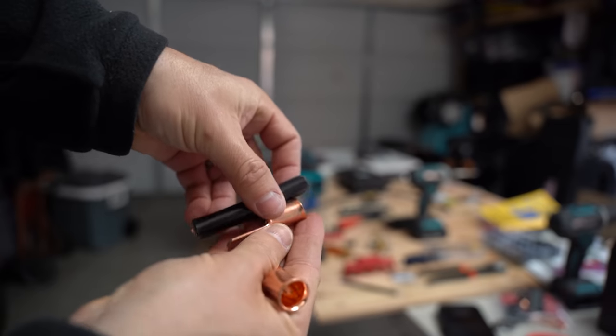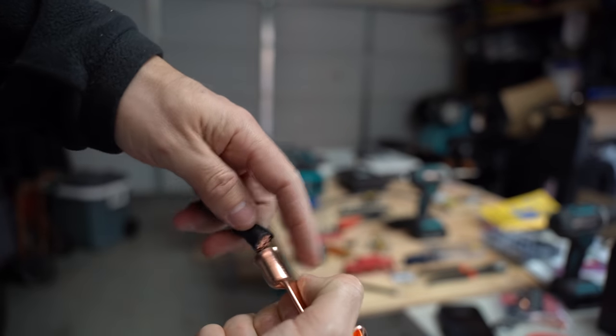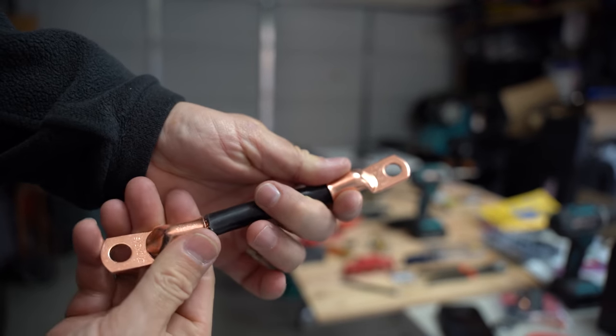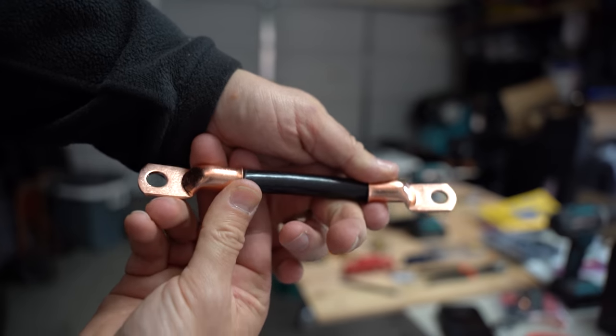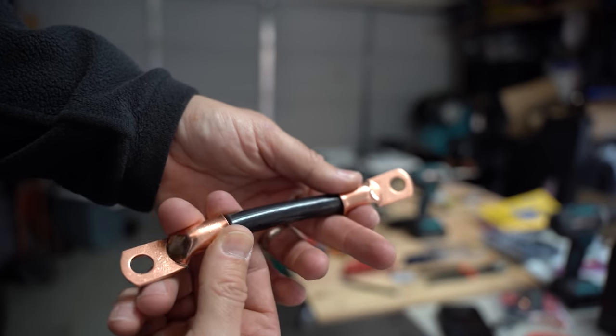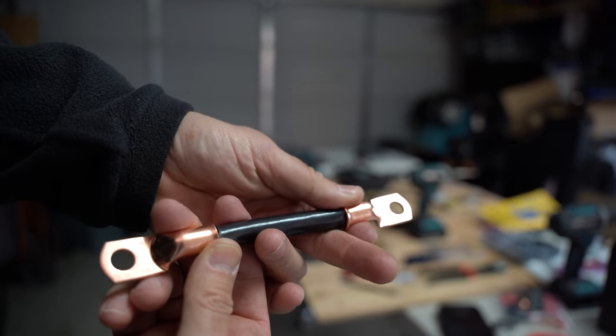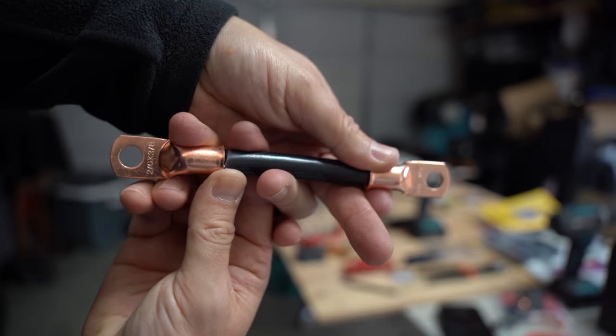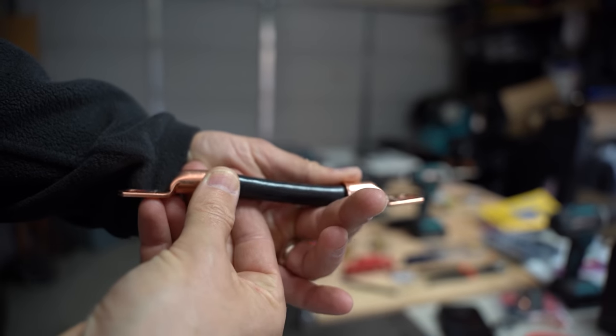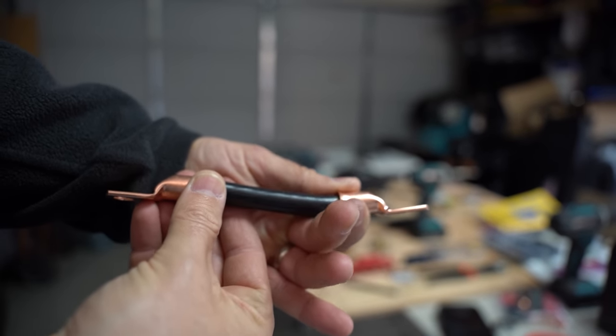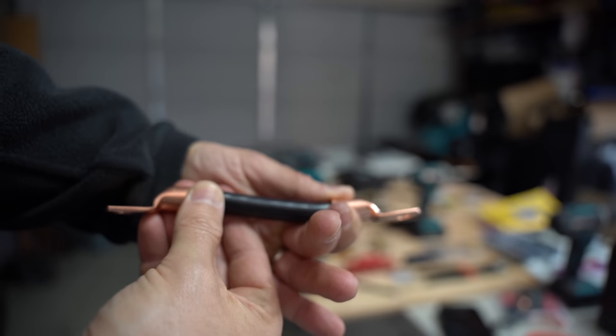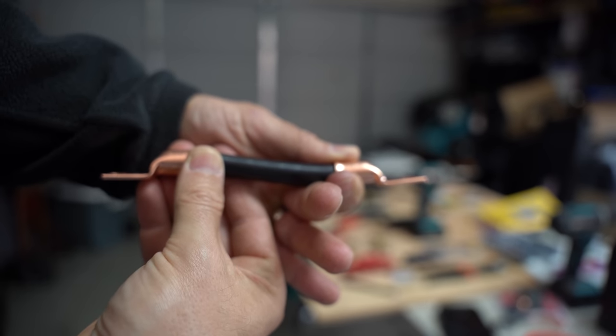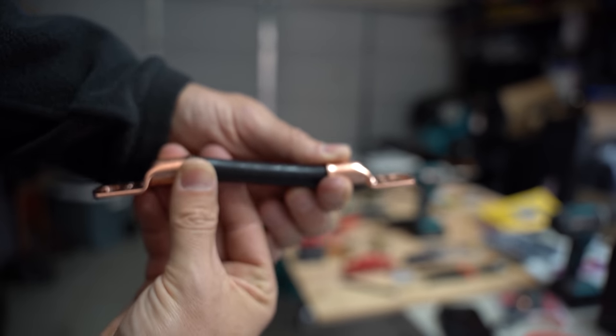Also remember, when putting these cable lugs on, please keep them at the same orientation. What do I mean? If we add one cable lug on one end and then we start the process to add the second lug on the other end, if the second cable lug was at a 90 degree angle to the first, I wouldn't be able to mount these on our inverter and fuse. So, as shown here, they're at the same angle relative to each other.